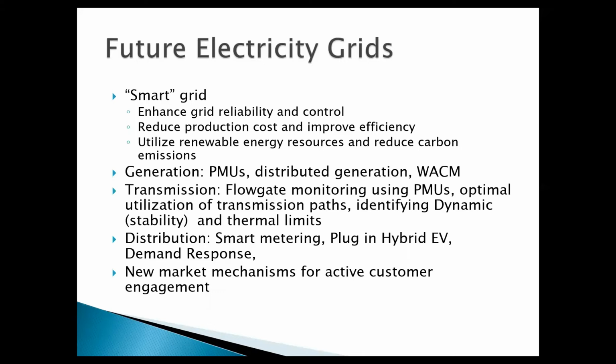On the transmission side, you'd say transmission is saturated, so why do you need anything else? Well, because of the infeed from photovoltaics, we're seeing a problem in Queensland where the QNI interconnector, a Queensland-New South Wales interface or intertie, is getting overloaded sometimes for the wrong reasons. It was designed to export power from one area to another, but now it's getting import from another area because of photovoltaics. So there's increased monitoring of these interfaces in coming years, because if you don't monitor them, there will be a stability problem. Those who understand power system stability know it's the angles which oscillate against each other when you have a heavy transfer of power from one area to the other.